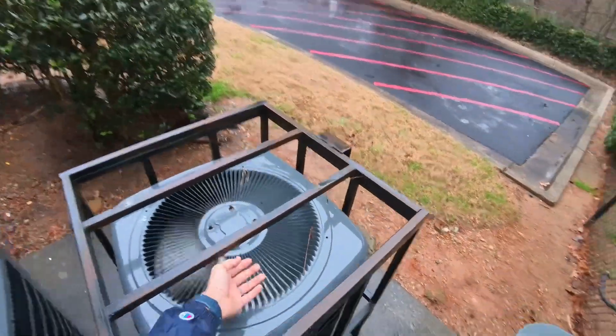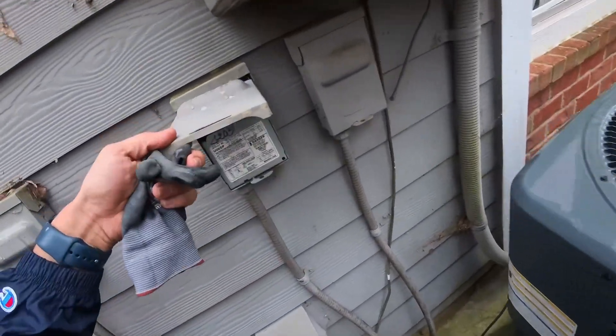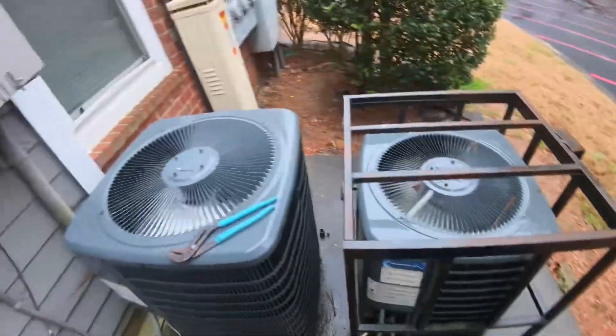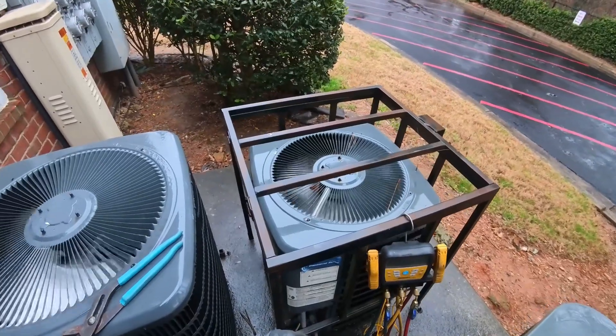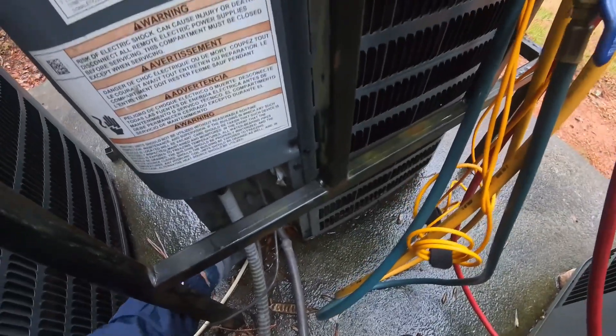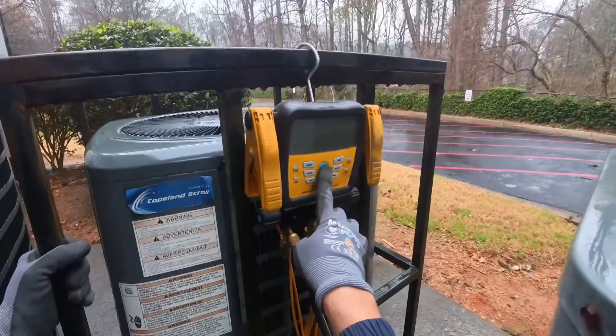I found which unit it is — it's this one. Is it going into defrost? Yeah, I think it just went into defrost. Kind of soon for it to be going into defrost. I cut these off — they're labeled right here, it's 4203. It is this unit, the only one with the cage. There's something going on, I think. Let me go get my drill. Let me check if this is an R22 system. Yeah, this is an R22 — so this is an older unit.